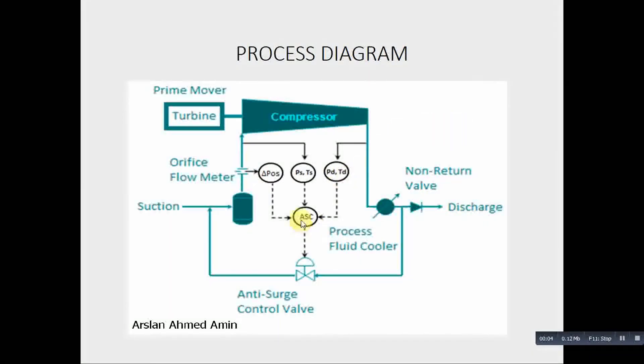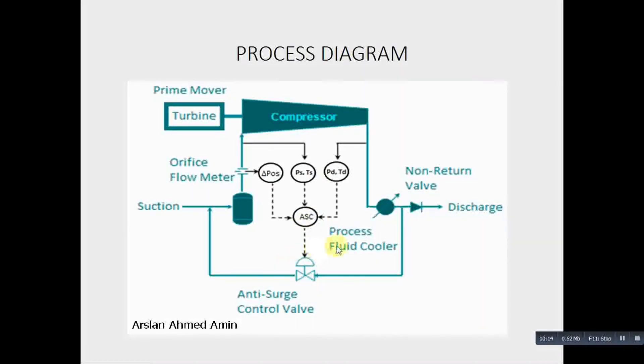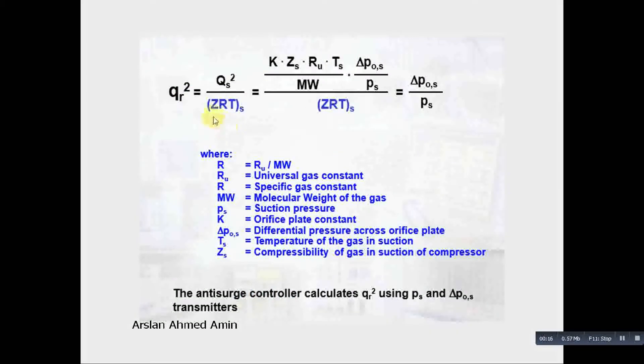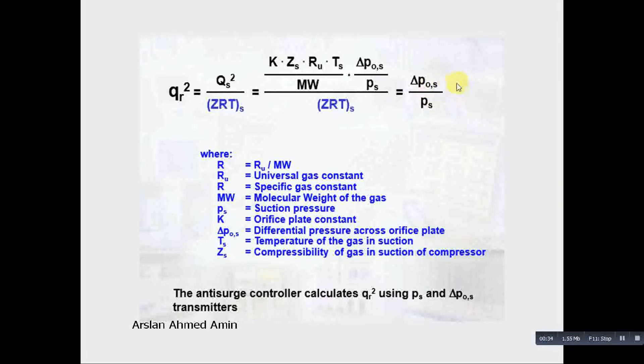The compressor's computer takes inputs from the field transmitters and generates an output. The 4-to-20 mA input to the computer is controlled accordingly. These are the formulas to build the Compressor Map. This is the qr squared reduced flow and the corresponding calculations. The resultant is delta P over PS — this is the flow transmitter reading and this is the suction pressure transmitter. From this ratio, we can get the qr squared.